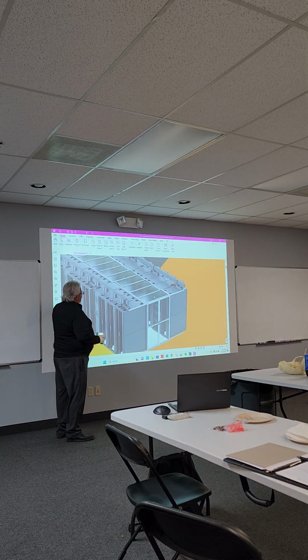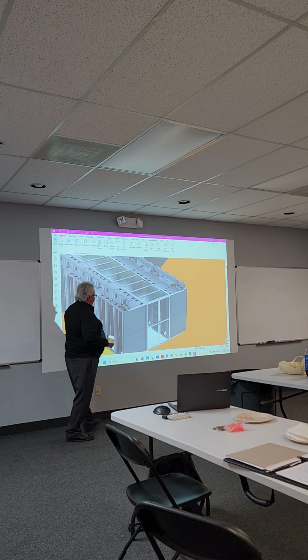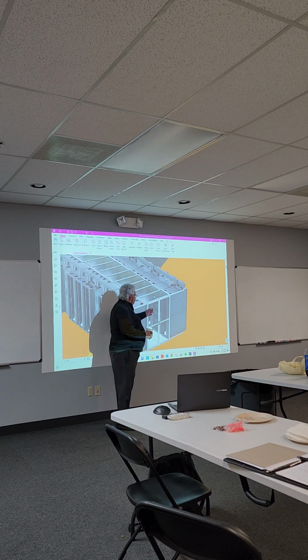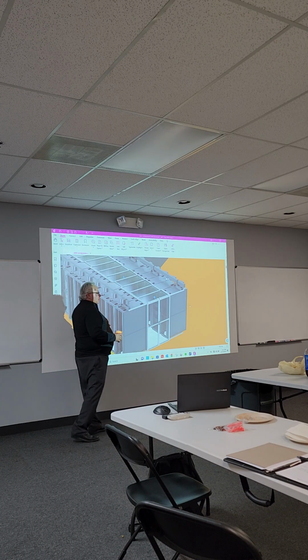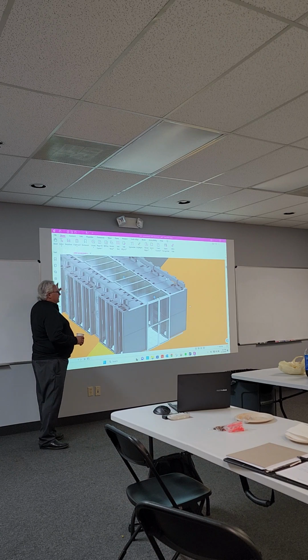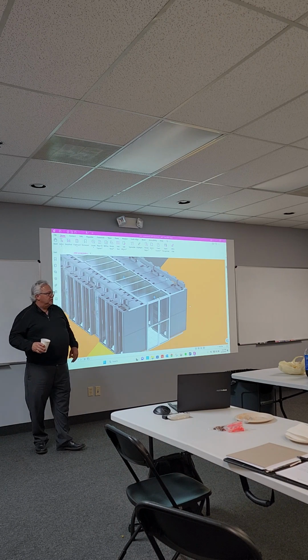Somehow, some way, you tell them: if you put doors at the end of the aisle to contain the heat or cooling, what's going to happen? That unit over there can now be put on a rotation with the rest of the units, or just let it run because the whole room's now a return air plenum.